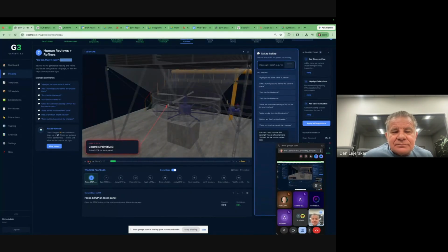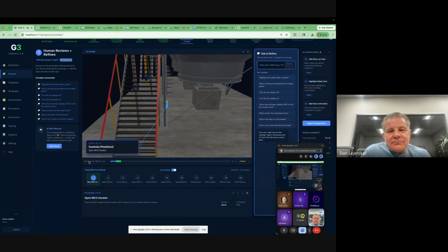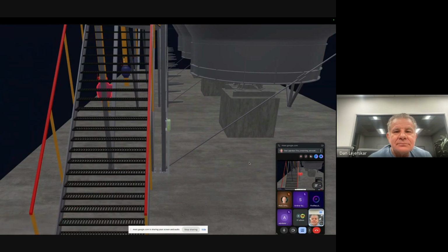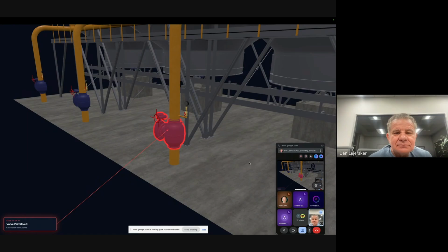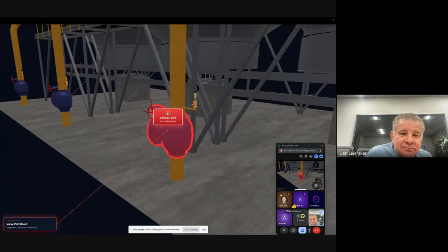Verify work permit, verify equipment tag, don PPE, notify control room, press stop on local panel. Walk to motor control center, open MCC breaker. Apply LOTO padlock to breaker. Attach danger tag. Verify 0 voltage at motor terminal box. Re-verify voltmeter on known live source. Close inlet block valve. And I can manipulate here while it's doing it. So apply LOTO padlock to inlet valve.